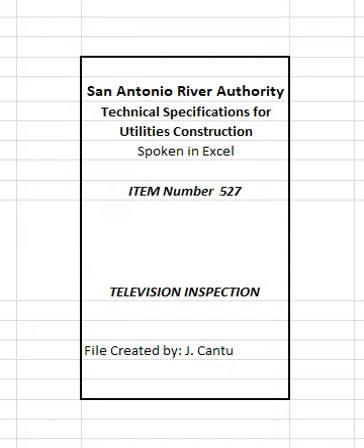A camera with rotating and panning lens capabilities is required. The camera height shall be centered in the conduit being televised. The speed of the camera through the conduit shall not exceed 40 feet per minute. The contractor shall be required to have all materials, equipment, and labor force necessary to complete all videotaping on the job site prior to isolating the sewer manhole segment and beginning videotaping operations. Television inspection shall be done one manhole section at a time.